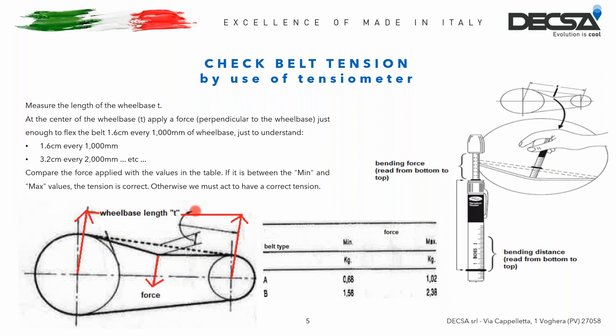As you can see, the wheel base T is the distance between the center of the two pulleys — the fan pulley and motor pulley. This distance must be reported perpendicularly on the belt, and then you must calculate its midpoint. On this midpoint, you connect a tensiometer — the right device for this job — to push the belt away from the near one by 1.6 centimeters if the wheel base T is one meter long, or 3.2 centimeters if it's two meters long, and so on.